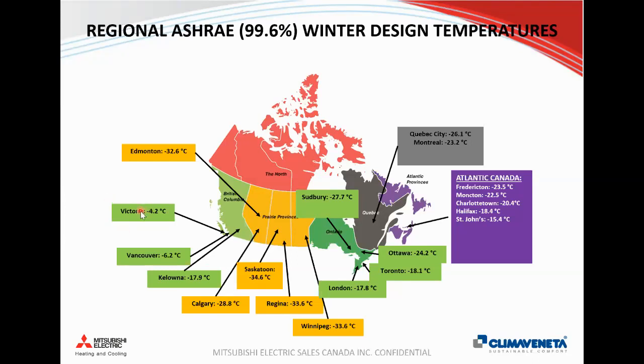Obviously the West Coast, Victoria, Vancouver, those are good heat pump markets, and they're doing new builds, high rise, with air to water heat pumps on the roof instead of boilers. And they can actually design these systems to eliminate the boiler altogether with their aggressive regulatory approach to banning natural gas in new buildings. That will start to escalate more for larger buildings over the next couple of years.